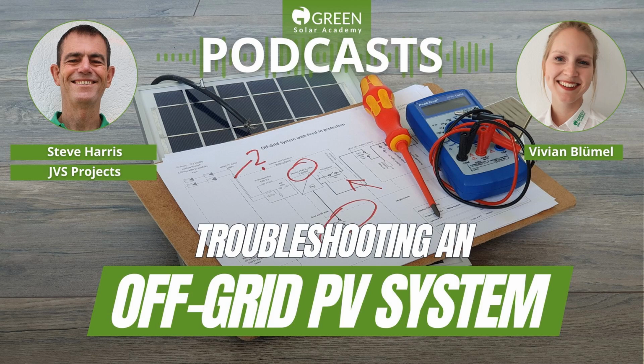So today might be 2 degrees hotter than yesterday, so it triggers today, or yesterday was 2 degrees hotter when they first noticed the fault. So what we've done a number of times where we've had reported faults, we've brought the inverters back to town, we've opened them up in the clean environments of our service centers, and discovered on a couple of them that they are absolutely caked solid with dust because the rooms have not been cleaned. There's just a lot of dust, and the inverters cannot cool down. So they run into overheat and they switch off. So for us in Africa, that's a really big problem, is overheating of the electronic components in the inverter.